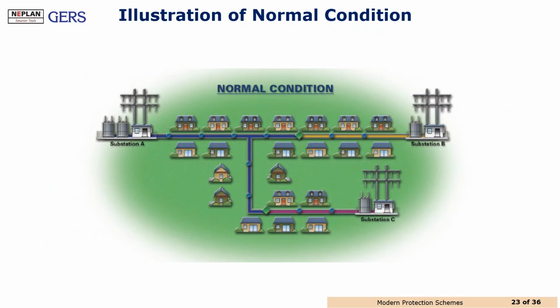To understand that in a better way, I have here an illustration of the FLISR application. We have here three substations, and maybe we can consider the substations as the connection to the transmission system or new generators on the distribution system that represent different sources. But it is very interesting that, for example, in this illustration, this breaker and this breaker are open, and that means that we have three feeders. Feeder in blue, feeder in yellow, and feeder in red.